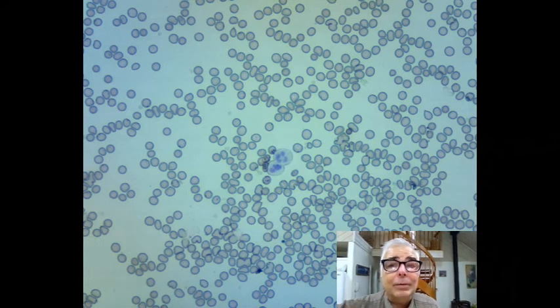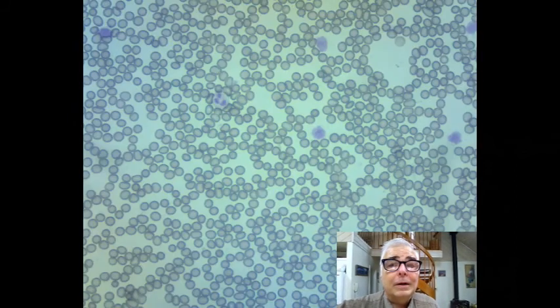And here is an area of the blood smear without enough red blood cells — you don't want to count here either. Here's a spot in the monolayer that has an appropriate number of red blood cells; their spacing is uniform and we can take a picture of this. I usually take my pictures at 100x magnification — that's the 10x objective lens and the additional magnification that the camera provides. That gives me a reasonable sample in terms of total area and a reasonable number of white cells per field of view.